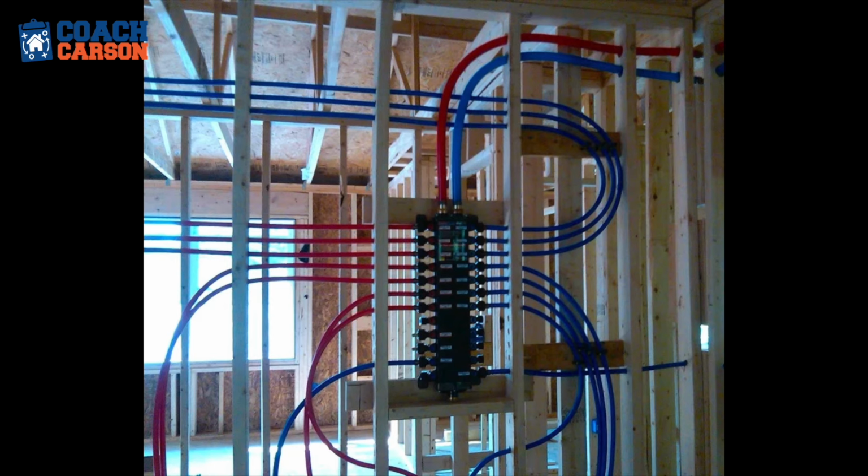If you're replumbing a house and you're doing it in PEX, one of the things is, are we going to just branch off a 3/4 line and then go a few directions with 1/2 inch to a vanity? Or are we going to go down to a common manifold, where every cold and every hot water line has an individual branch, and then that goes to a manifold with a shutoff, so you can shut off every single little branch. It's super handy. It costs a little bit more, but it is great for serviceability later on.